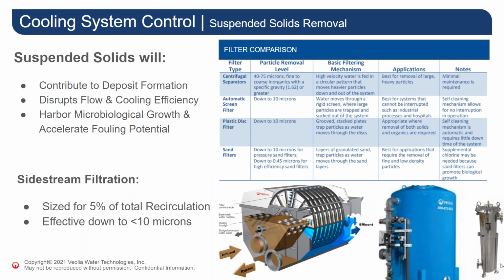So, beyond the chemical treatment, there's a number of mechanical devices that we recommend that can greatly improve the operation of a cooling system. As we mentioned, a cooling tower acts much like a giant air washer, drawing in huge volumes of outside air. So anything in that air will end up in the tower. Anyone who has ever had a plant operating next to a large farm operation has seen what that cooling tower can suck in, especially during spring tilling and planting.